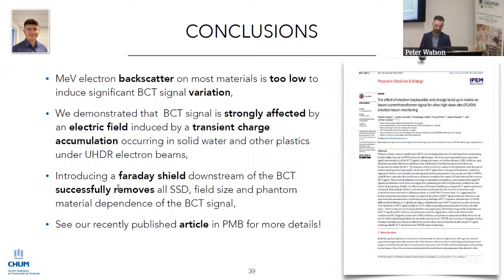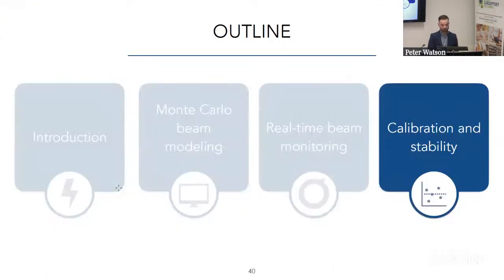Introducing an electrostatic shield downstream of the BCT successfully removed all the SSD, field size and phantom material dependence of the BCT signal, and all the details were published in a paper in PMB earlier this year. So once we had this nice tool, once we corrected this very promising tool to monitor the beam, we wanted to know how accurate it could be. Once you get rid of this artifact, how accurately can it actually track the dose?